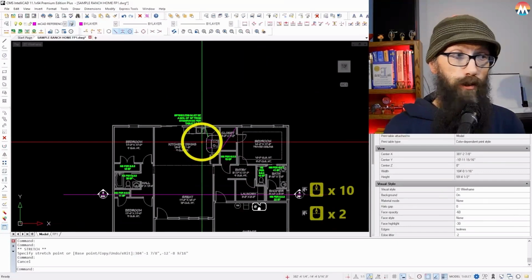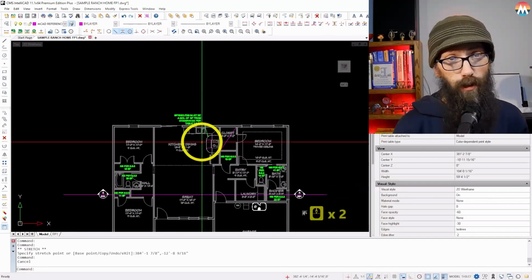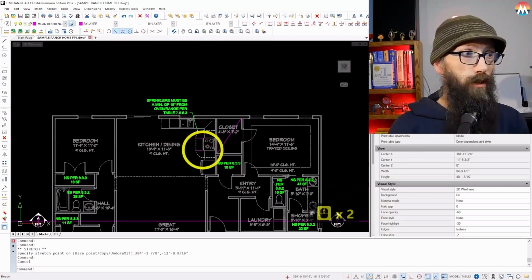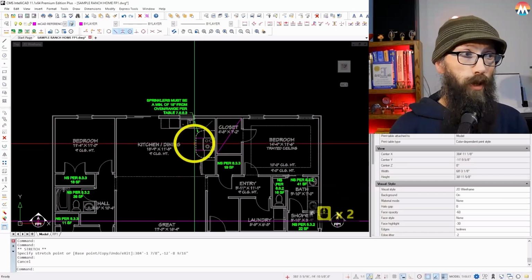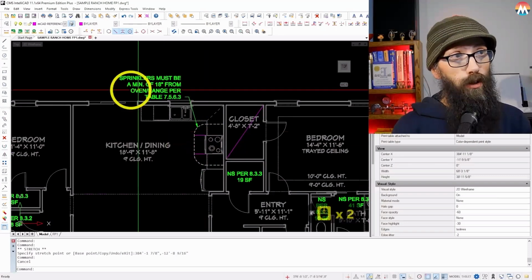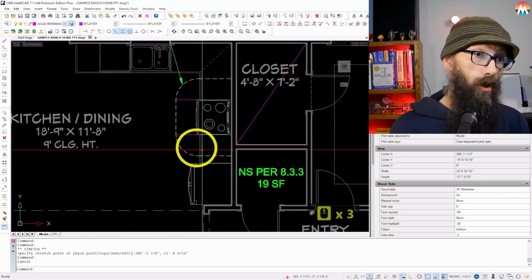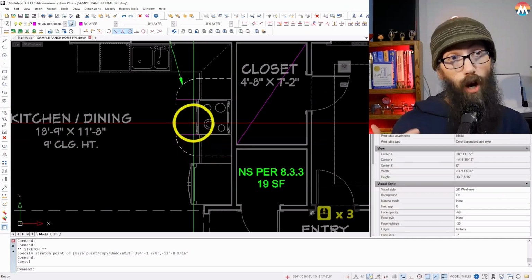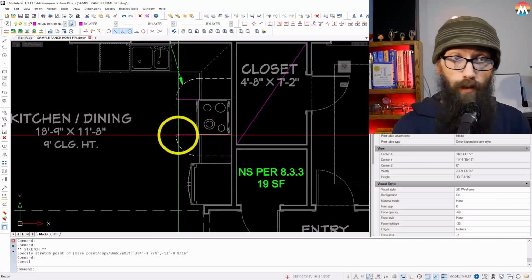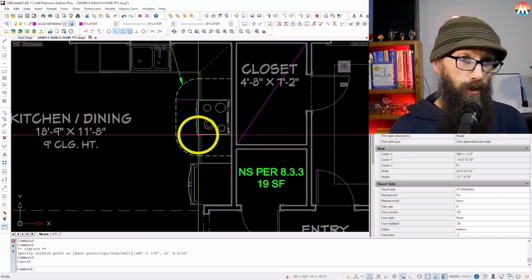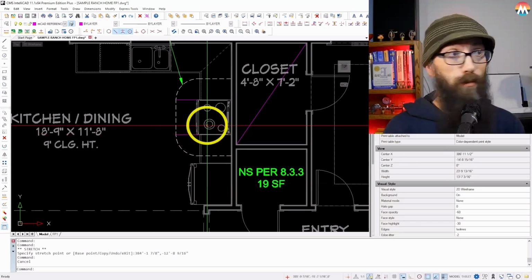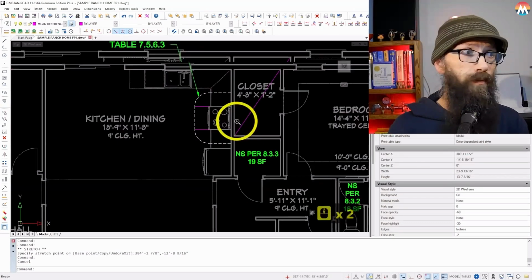That's our only heat source of concern in this project. But basically, that gives you the idea. We are just marking these lines around. We have them already set up. It's 18 inches away. We drew that 18-inch line. This is an 18-inch arc that I already have drawn, and we're just dropping it on this line that puts us in the correct position 18 inches away from the oven. Couldn't be too much simpler.